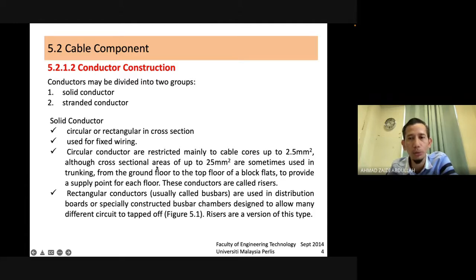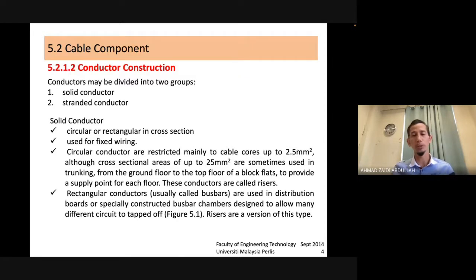Although cross-sectional areas up to 25 mm are sometimes used in trunking, mostly from the ground floor to the top floor of a block of flats to provide a supply point for each floor. For your assignment later, you need to justify which type of cable you want to use, especially the conductor. Let's say you want to use 2.5 mm, so is it a solid conductor or stranded? You need to explain a little bit. Rectangular conductors, normally we call them bus bars, are used in distribution boards. That one is not related to our topic, because we are on the cable topic. Even though the function is the same, bus bar and cable both transfer energy from one point to another, this topic only covers cable.